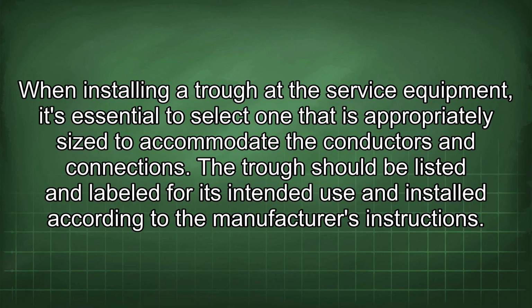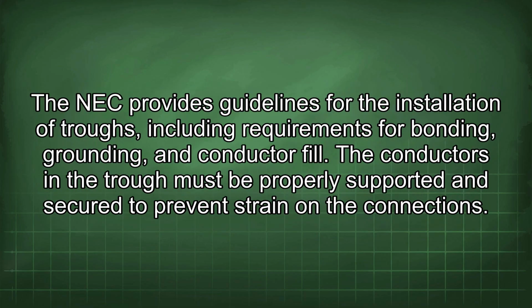When installing a trough at the service equipment, it is essential to select one that is appropriately sized to accommodate the conductors and connections. The trough should be listed and labeled for its intended use and installed according to the manufacturer's instructions. The NEC provides guidelines for the installation of troughs, including requirements for bonding, grounding, and conductor fill. The conductors in the trough must be properly supported and secured to prevent strain on the connections.